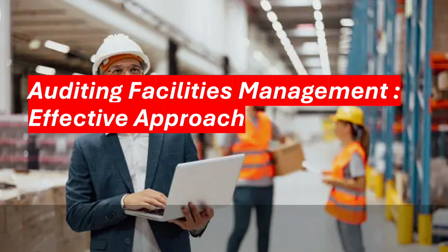Criteria. Policy states all emergency exit lights must be tested monthly, with logs kept for 3 years. Condition. The log shows only 60% of tests were completed last quarter. A walkthrough found 2 non-functional lights. Cause: the assigned staff member was not trained, and there is no supervisory oversight. Effect: high risk. In a power outage, occupants could be injured during an evacuation. Potential for regulatory fines and reputational damage.